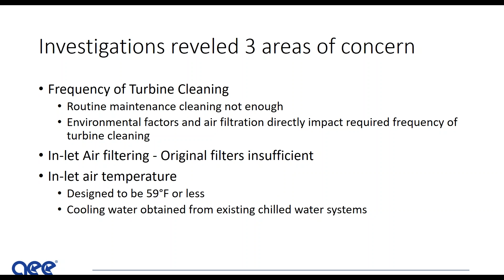The third was inlet temperature. We designed for 59 degrees, but the chilled water system did not always hit that. We pulled water from the chilled water system, which has a temperature control question on it, so it varies a little bit. Not a lot, but a degree or two does mean something. We were instrumented well enough that we knew what to look for.